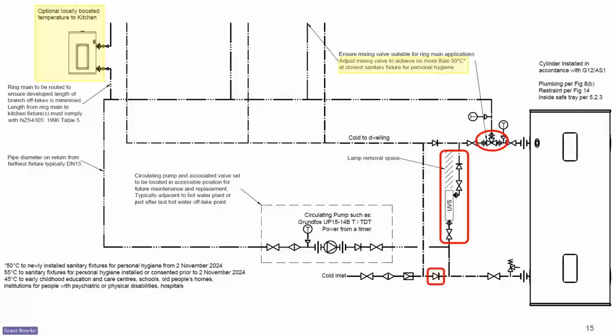Again, it's really important that the cold water connection to the mixing valve is what I call virgin cold water. I've seen installations where the cold water expansion valve is the other side of this connection, and there's lukewarm water going up this cold connection to the mixing valve. It doesn't tend to become dangerous, but it exhibits itself as temperature fluctuations at times in the ring main. And given that you've installed these perhaps in your most discerning customers' houses, having temperature fluctuations is not a wonderful thing.